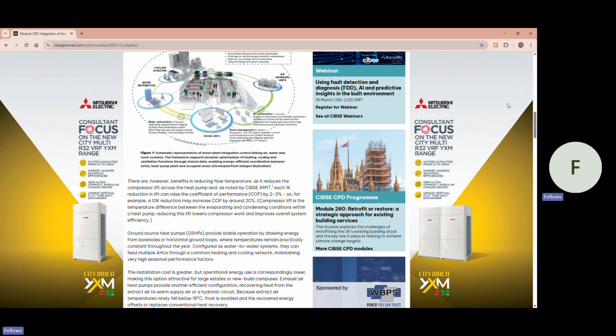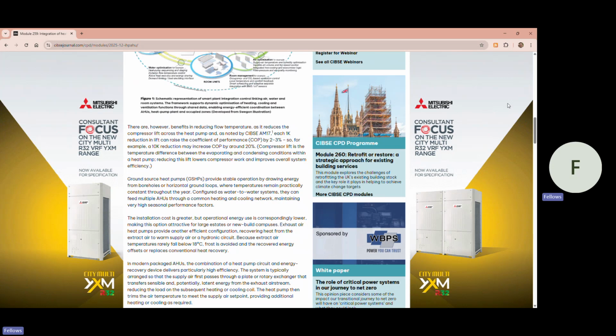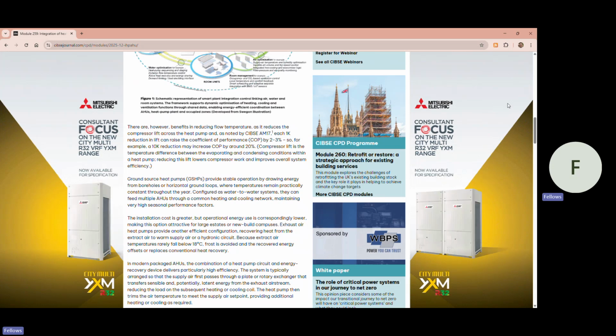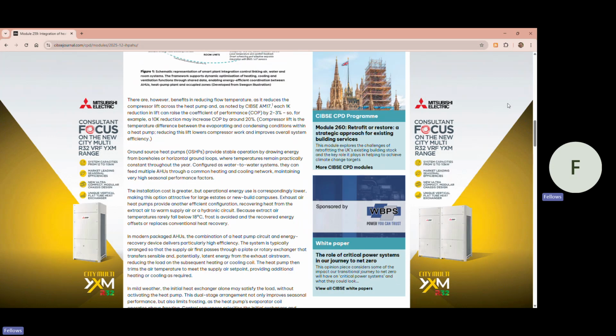Compressor lift is the temperature difference between the evaporating and condensing conditions within a heat pump. Reducing this lift lowers compressor work and improves overall system efficiency. Ground source heat pumps, or GSHPs, provide stable operation by drawing energy from boreholes or horizontal ground loops, where temperatures remain practically constant throughout the year. Configured as water-to-water systems, they can feed multiple AHUs through a common heating and cooling network, maintaining very high seasonal performance factors. The installation cost is greater, but operational energy use is correspondingly lower, making this option attractive for large estates or new build campuses.